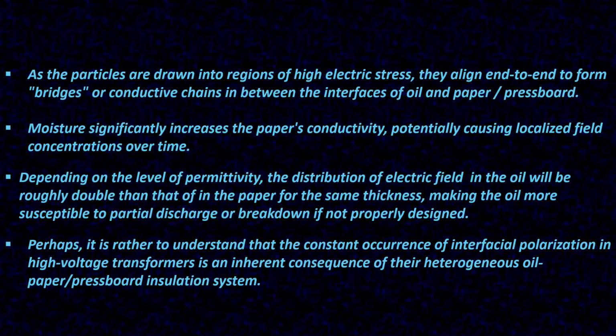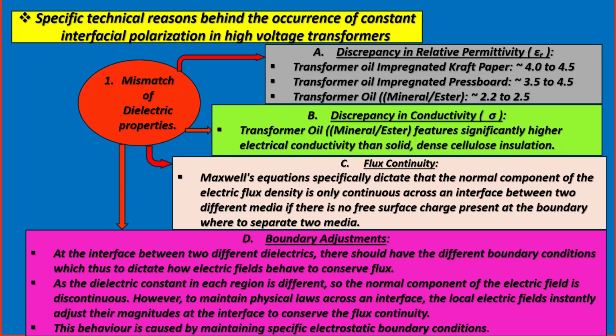Perhaps it is rather to understand that the constant occurrence of interfacial polarization in high voltage transformers is an inherent consequence of their heterogeneous oil, paper, pressboard insulation system. That is the reason interfacial polarization is much more detrimental so far as high voltage transformers are concerned. Specific technical reasons behind the occurrence of constant interfacial polarization in high voltage transformers. Number one, mismatch of dielectric properties.